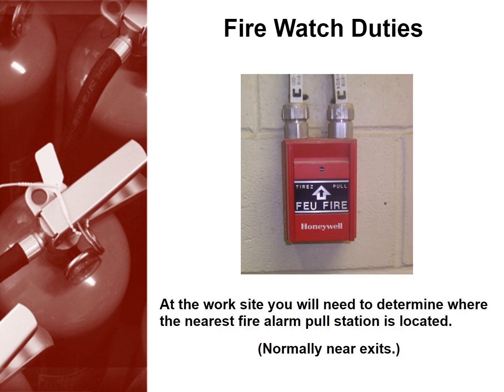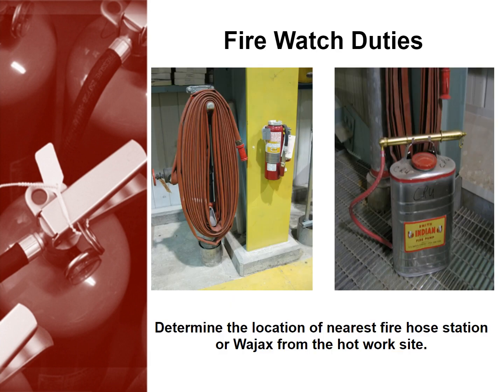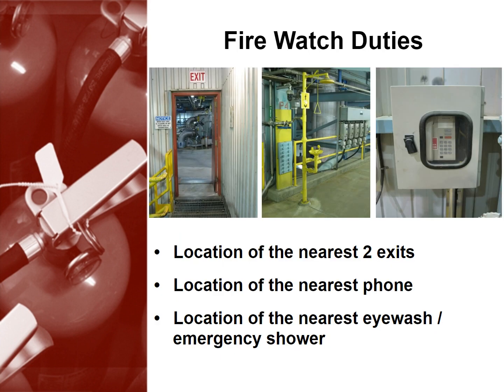Once at the worksite, you will need to determine where the nearest fire alarm pull station is located — these are usually near the exits. Then determine the location of the nearest fire hose station or Wajax from the hot worksite. Finally, you'll need to be aware of the location of the nearest two exits, the nearest phone, and the nearest eyewash or emergency shower.